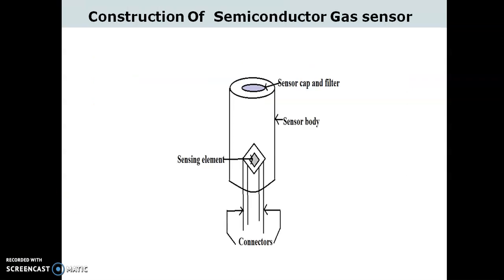Let us see the construction of semiconductor gas sensor. It consists of metal oxide film as a sensing element. The exact metal depends upon the gas to be detected. The film is connected to the electrodes and from the electrodes the connecting wires are taken out for the measurement of resistance. This sensing element is covered with the sensor body having the sensor cap and the filter at the top of its construction.